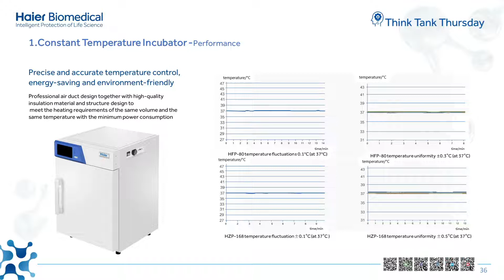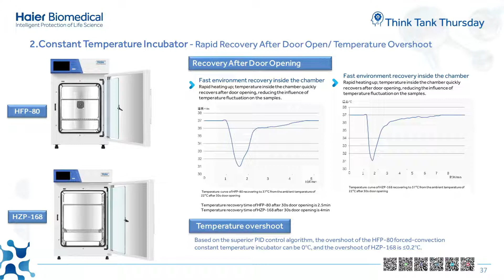Next, the temperature recovery after the door opens and closes on the constant temperature incubator. From the recorded graph we can see that both models clearly recover the inside temperature very quickly after the door opens, which reduces the temperature fluctuation on the sample. The recovery time of HFP-80 after a 30 second door opening is 2.5 minutes, and the recovery time of HZP-168 after a 30 second door opening is 4 minutes. Besides, with the superior PID control algorithm, the temperature fluctuation for the HFP forced convection constant temperature incubator can be 0 degrees, and for HZP-168 it is less than or equal to 0.2 degrees.